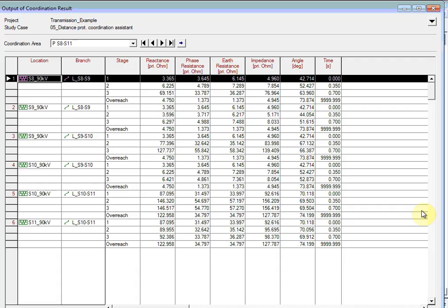Let's take a look at the settings in more detail. For the relay installed at the 90 kV substation 8 in the branch S8 to S9, you can see that settings have been defined for 3 main zones and an overreach zone. Reactance, resistance, earth resistance, impedance, angle, and time settings have been calculated. You can see that the time settings clearly follow the rules that were specified in the assistant.